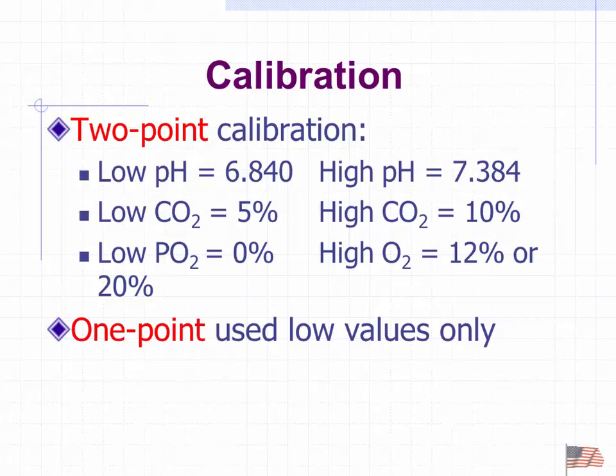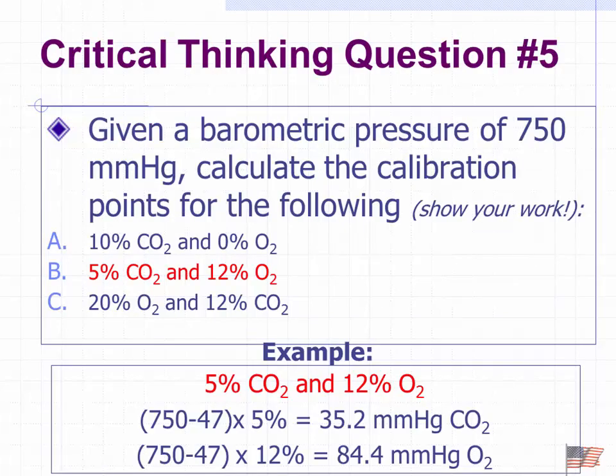There's what is called a 2-point calibration and a 1-point calibration. A 2-point, as the name implies, means I'm looking at the pH, PCO2, and PO2 at 2 different points. And I'm calibrating it to a low point, and I'm calibrating it to a high point. A 1-point, as the name implies, just picks one value and calibrates to that one value. So here's an application of, let's see, John Dalton's law. If I know the barometric pressure and I know the concentration of the gas that I am using, CO2 and O2, I can determine what the partial pressures should be.